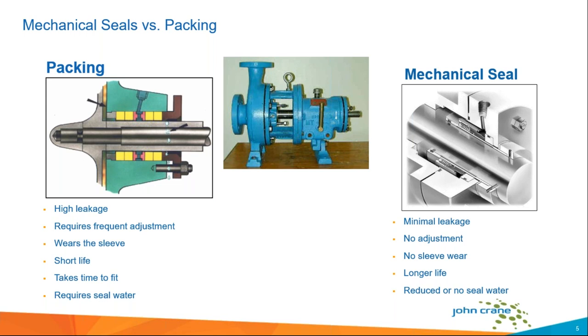There are three basic sealing choices used to keep centrifugal slurry pumps from leaking. The most common is a stuffing box that uses braided fiber packing material to smother as much leakage as possible. Another choice is called an expeller seal. And then there's the option we'll be looking at today: mechanical sealing technology — a set of very close clearance faces that run on a thin film of lubricant.